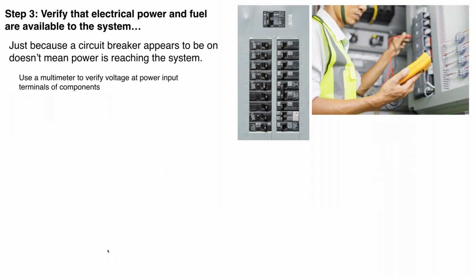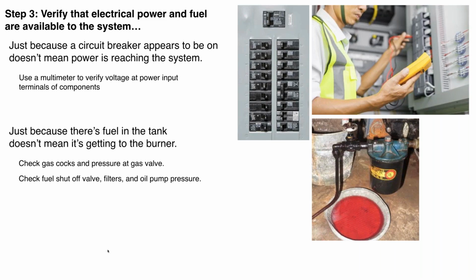Verify electrical power and fuel supply. In the last couple of years, I've had occasion to replace at least 2 circuit breakers that were relatively new, but simply failed. So just because a circuit breaker isn't tripped doesn't mean that you necessarily have power output. You've got to put a meter on there and check that, okay? Just because the fuel gauge on an oil tank shows maybe half a tank of oil, maybe somebody closed this valve, maybe this filter is plugged, okay? You've got to check for fuel supply to make sure that if it's a boiler, the food that boiler needs is available to it. So filters, valves, and checking power supply.